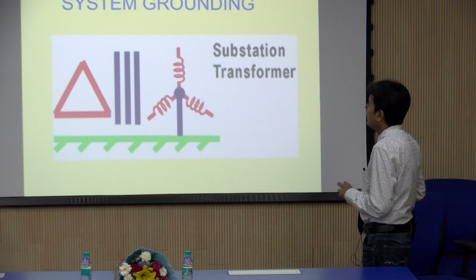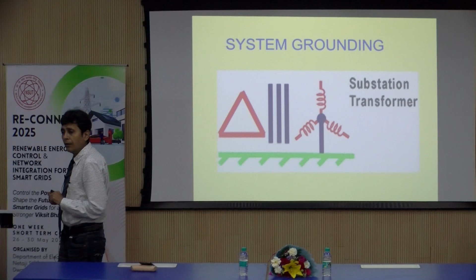When I say grounded systems, again there are 2 components that come into the picture: equipment grounding and system grounding. Equipment grounding takes care of the equipment and the persons who are going to touch your equipment during the fault. And system grounding fixes the voltage with respect to earth, to do the proper insulation coordination, to choose the proper insulation requirement. System earthing plays a vital role.